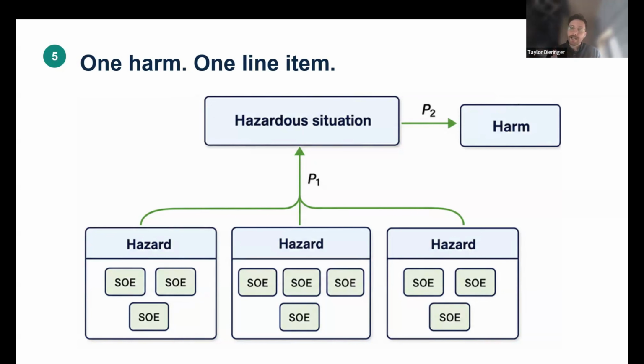This is really just demonstrating the entryway to our investigation phase. From complaints at the top, we go down into our hazardous situation harm pair. And if we identify that there is some type of signal as a result of the data we're getting from the field, then we can drill down into our individual states or conditions of the system and sequences of events in our investigation phase. So it acts as an entryway into that investigation rather than something where we have to sift through many individual documents to come up with a unique and illustrative fishbone diagram.